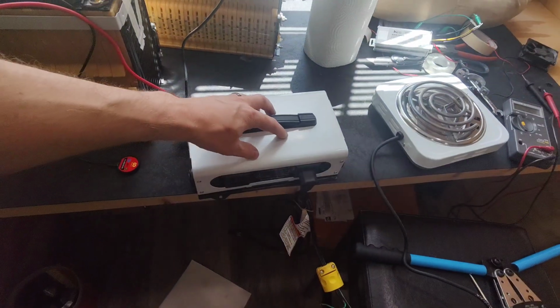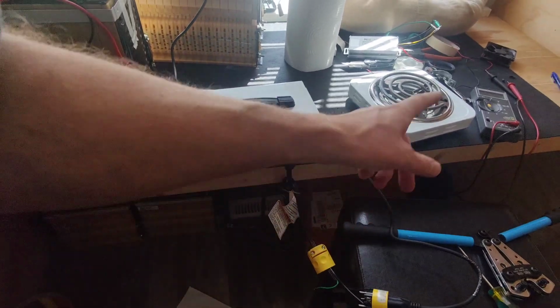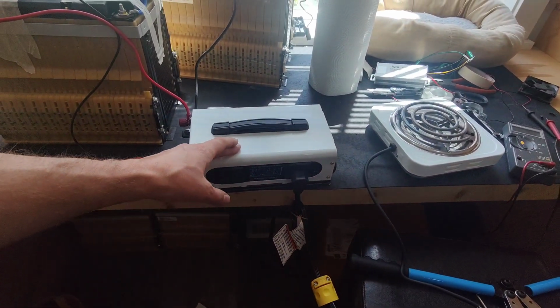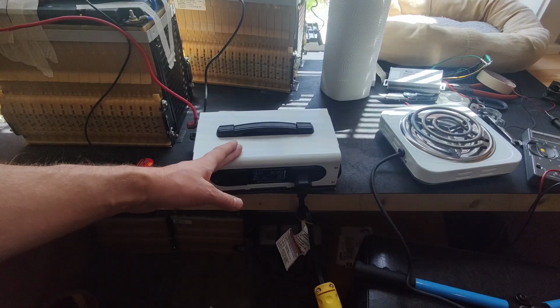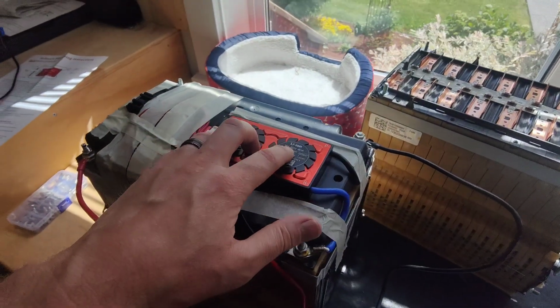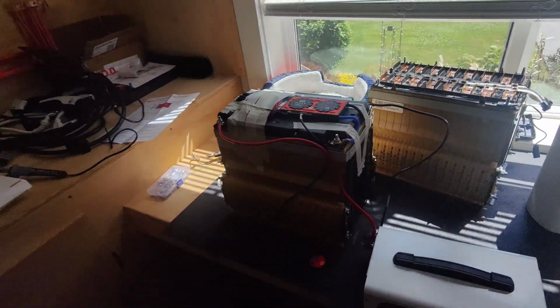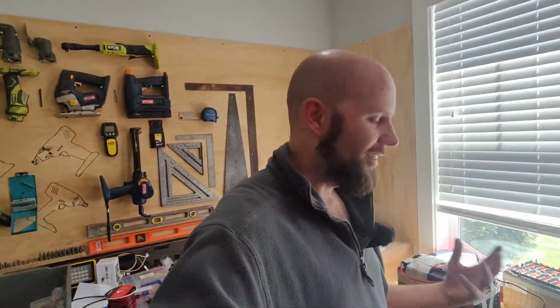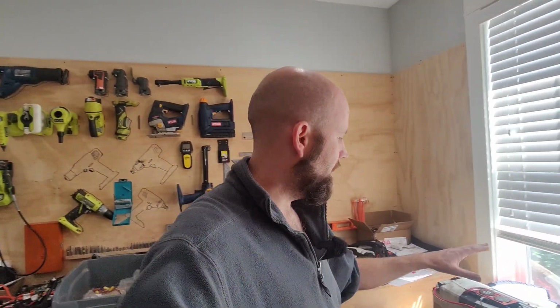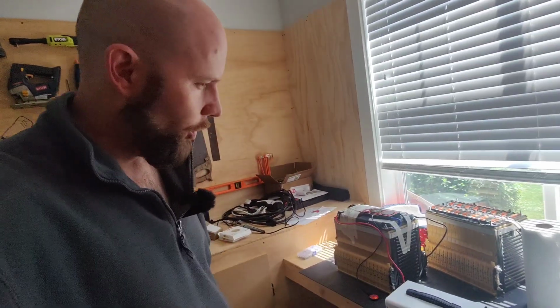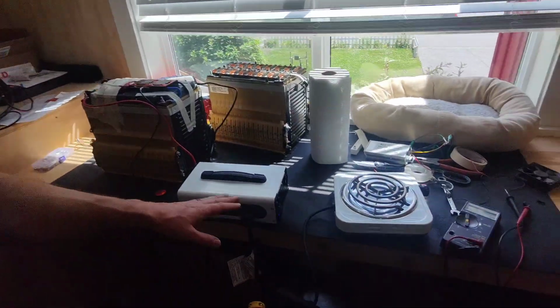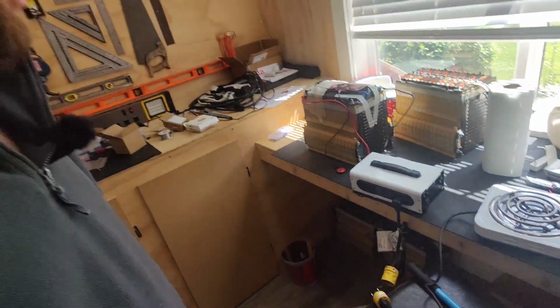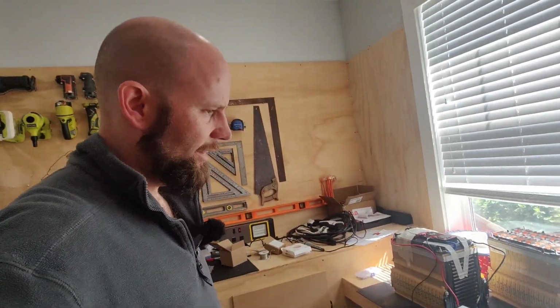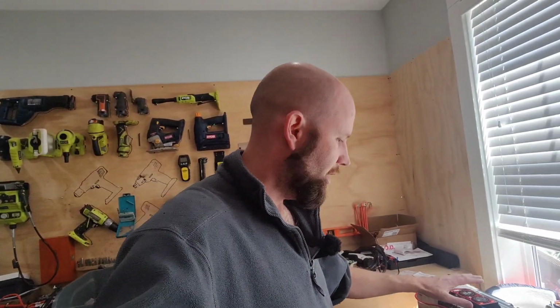This doesn't draw 40 amps. Basically this is capable of outputting a maximum of about 1500 watts, a surge of about 3000 watts. So 60 times 40 really is only a maximum of 2400 watts. I need to make sure I don't exceed a draw of 2400 watts, because that will just trip the BMS. I don't see going above the constant capability of this inverter, which is 1500 watts anyway, but I'll have a surge capability of 2400 watts absolute maximum drawing through this BMS.